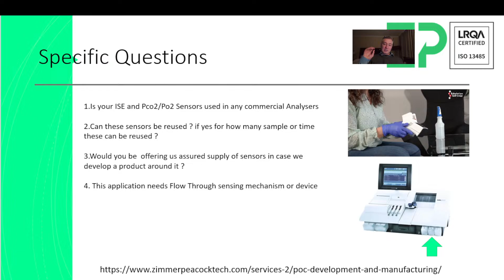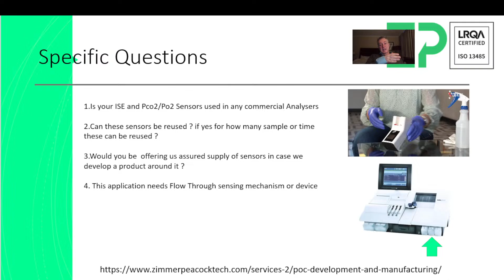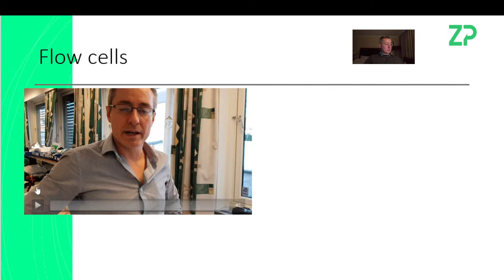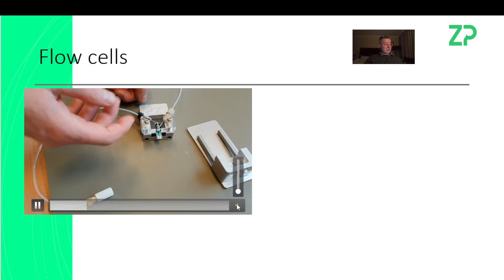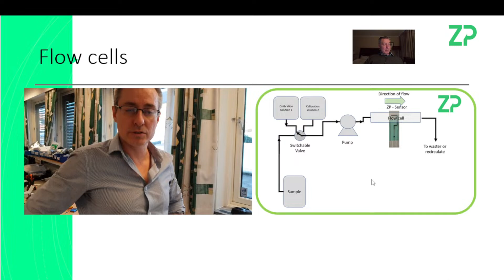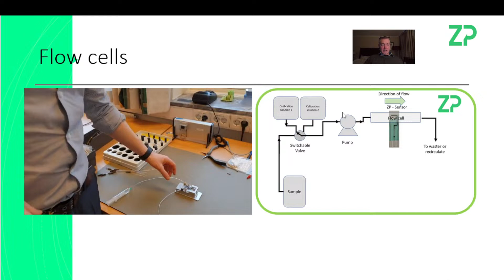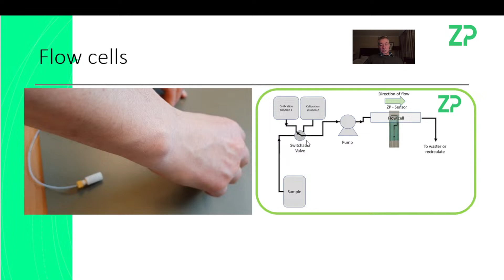They're asking here about flow-through sensing because in these chemical analyzers, the samples, the calibration solution and the wash solutions actually flow across the electrochemical cells. So at ZP, we do have some technologies where we demonstrate that we can take our electrodes, put them into a little flow cell, and flow solutions over the top. And I have some designs here for the idea that a sensor is in a flow cell. You have things like the sample itself, which could be a blood sample in this case, switching valves, calibration solutions, and pumps. So at ZP, we're quite familiar with putting these electrodes into flow systems.